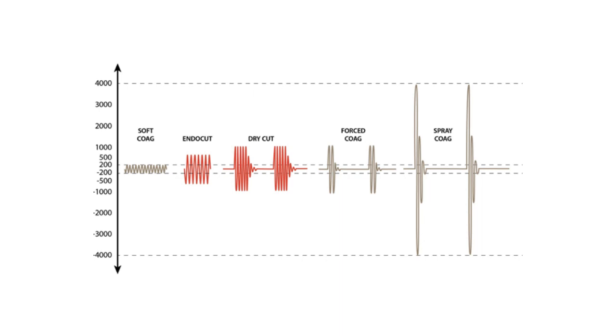When it comes to cut, endocut has a voltage of more than 200 volts without interruption. And with dry cut, you do have some interruption because there is a lot more coagulation compared to endocut.